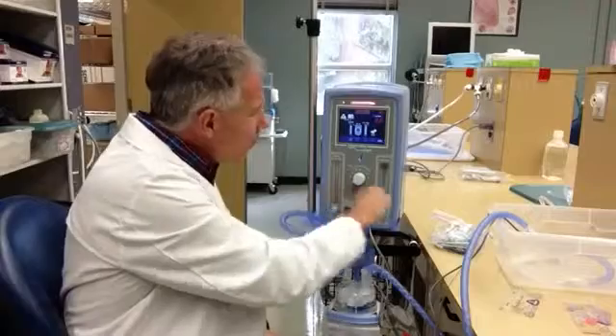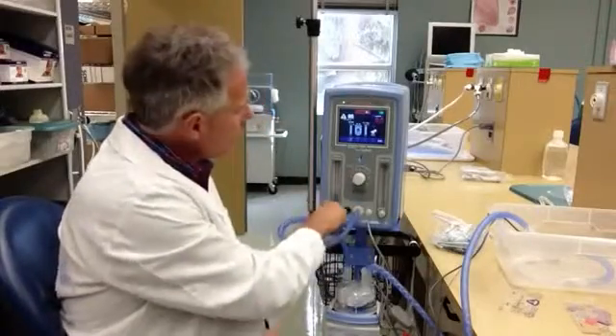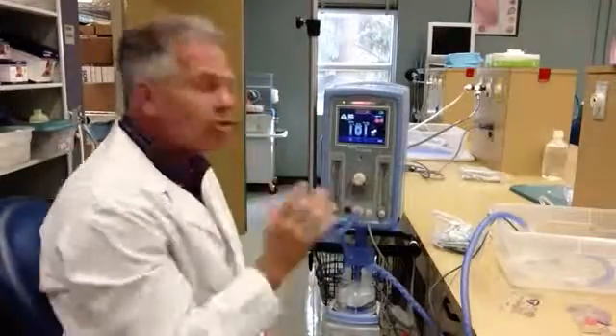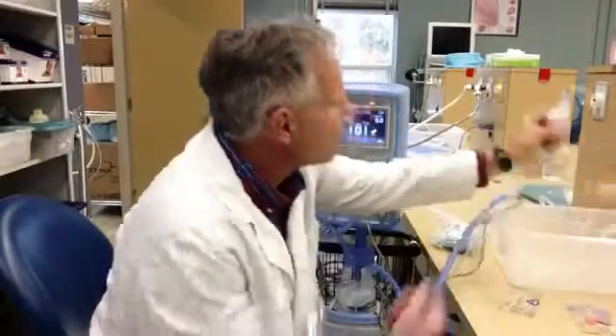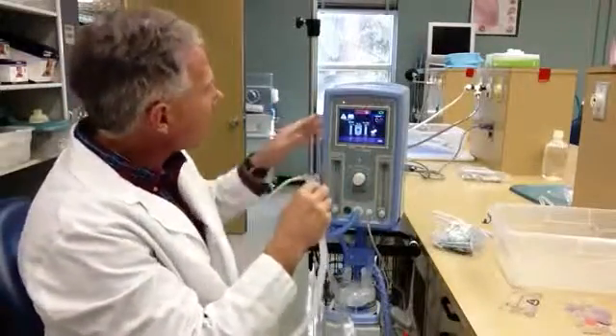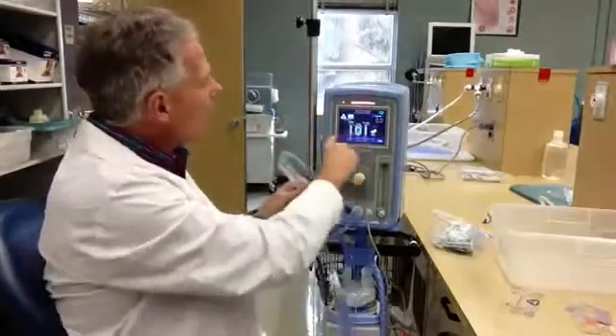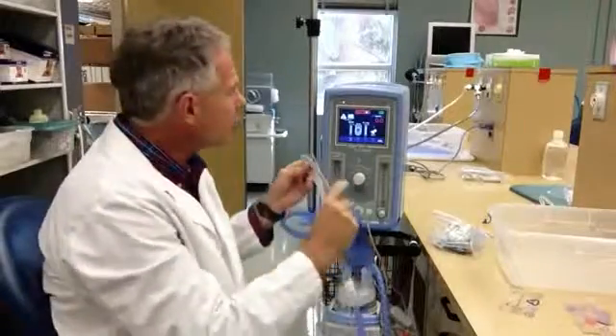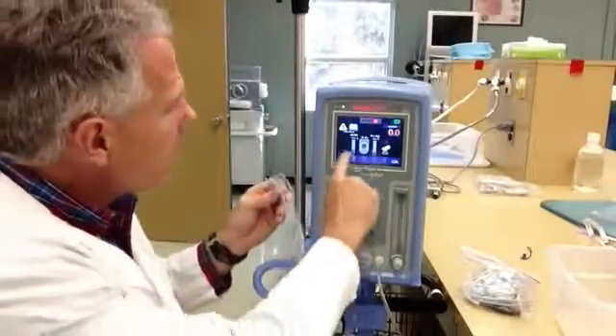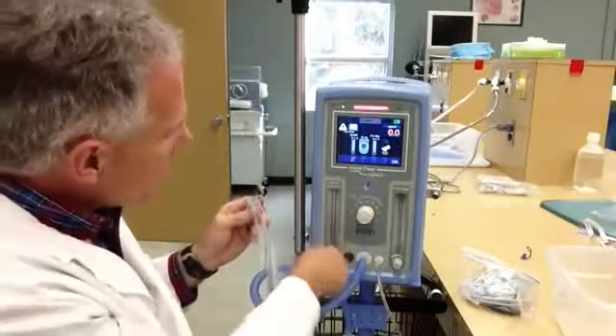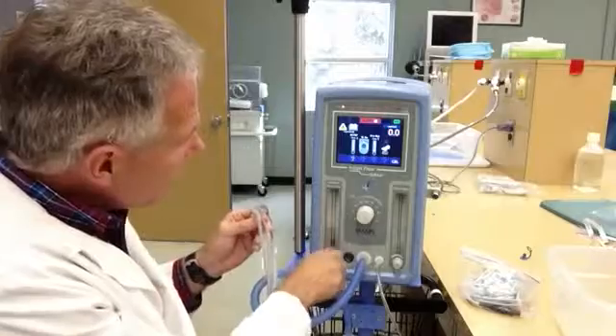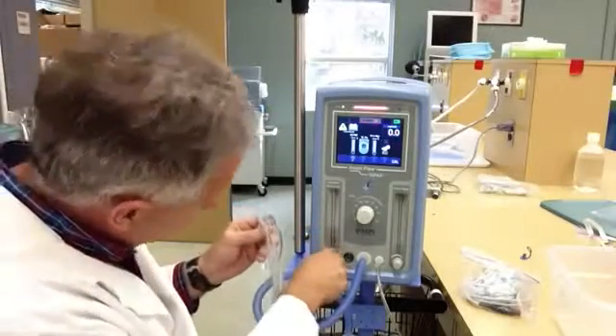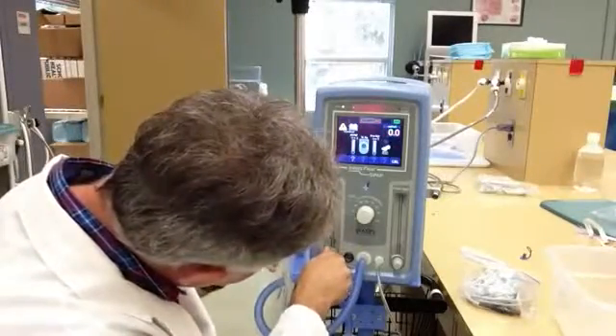All right. Now I've turned the flows off. Okay? So I've turned them all the way clockwise, so there's no flow going through the device at this time. All right? So we'll need our little patient connector right here. And it's asking me now to do my checkout. So it actually prompts you to do your checkout. You can come in here a little closer so you can see that screen. All right? So the first thing we want to do is check our nasal CPAP out. So I'm going to set the nasal CPAP flow to 8 liters per minute.